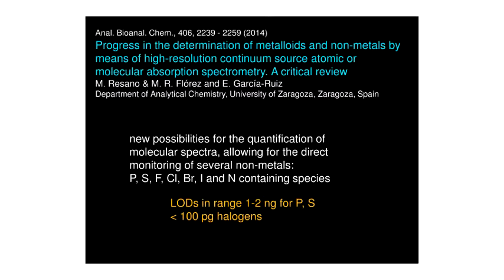Another aspect of high-resolution continuum source instrumentation is the ability to look at elements not amenable to classic atomic absorption, such as phosphorus, sulfur, the halogens, and nitrogen. By looking at molecular forms, you have an instrument capable of isolating the rotational-vibrational structure of molecules such as phosphorus oxide, sulfur oxide, magnesium chloride, or magnesium bromide — by adding a metal to the sample to form a molecule, you can look at the absorption by that molecule.